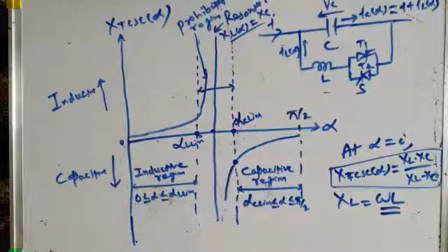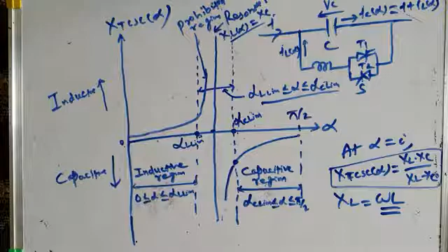And within this range, that is alpha L lim to alpha C lim, you should not operate your TCSC at all, because within this region, a resonance condition occurs, and at resonance, the TCSC reactance becomes infinite, and no transmission line current flows. Reactance becomes infinite. So this is the prohibited range, and this range is from alpha L lim to alpha C lim. You should never operate your TCSC within this range, because it is the prohibited range. It's the range very close to parallel resonance. So I hope this is clear.